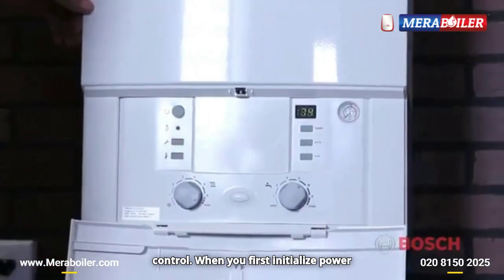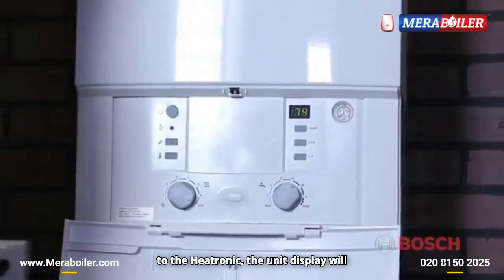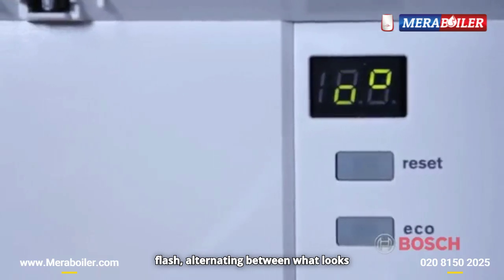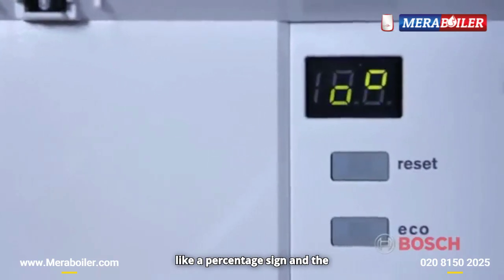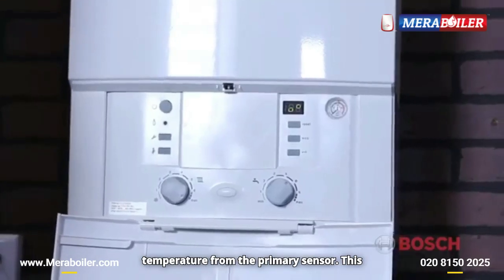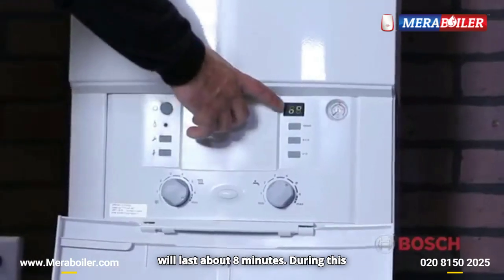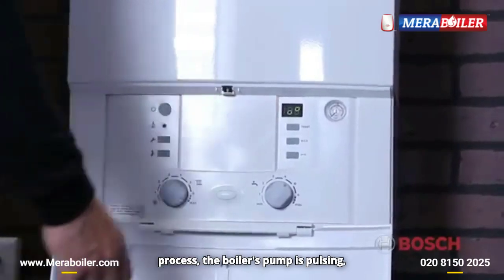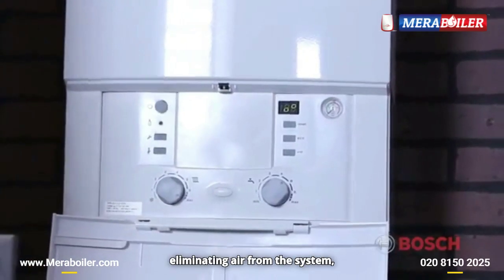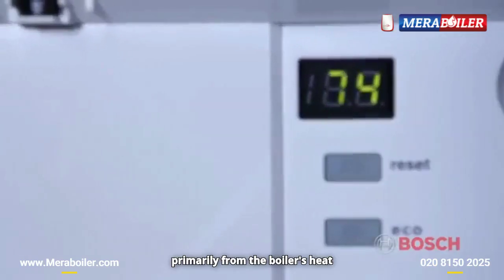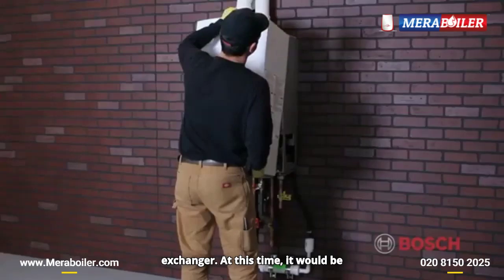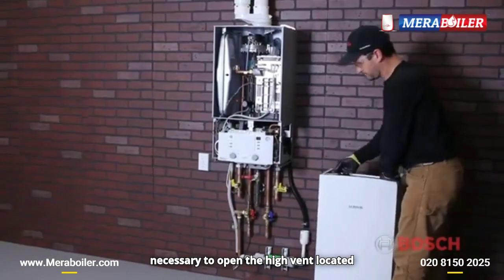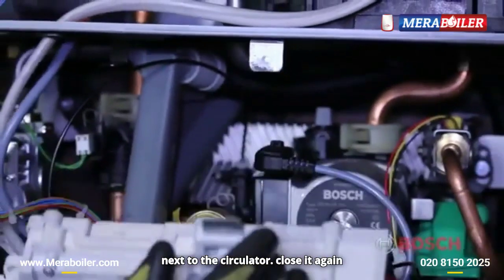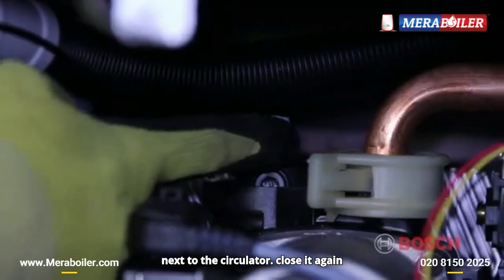When you first initialize power to the Heatronic, the unit display will flash, alternating between what looks like a percentage sign and the temperature from the primary sensor. This will last about 8 minutes. During this process, the boiler's pump is pulsing, eliminating air from the system, primarily from the boiler's heat exchanger. At this time, it would be necessary to open the air vent located next to the circulator. Close it again when the purging sequence has finished.